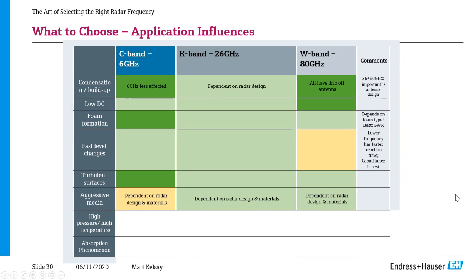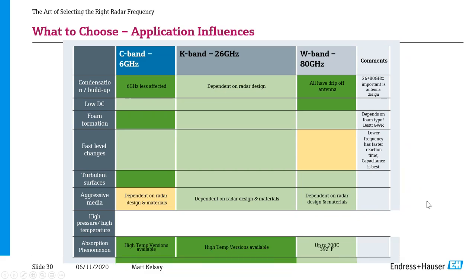So PTFE Teflon is your only wetted part with that design, and it's a very inert material compatible with many, many products. On our other styles, we do have alloys and different exotic materials available for those applications, but that generally comes with a higher price tag. So if you can use Teflon in the application, generally that's the way we'll go.